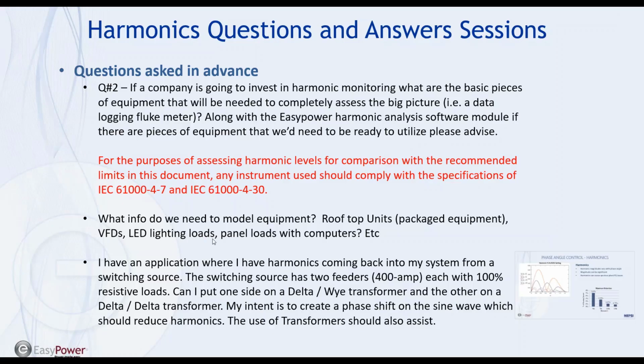Okay, so next question. I have an application where I have harmonics coming back into my system from a switching source. The switching source has 2 feeders, 400 amp, each with 100% resistive loads. Can I put one side on a delta, one side on a Y transformer, and the other on delta Y? So we're actually talking about doing delta Y and delta transformation for a load. This is typically done with a VFD drive, where you're taking 2 6-pulse drives and you end up with a 12-pulse device. All right. So in this case, the person is looking to create a phase shift on the sine wave, which should reduce harmonics.